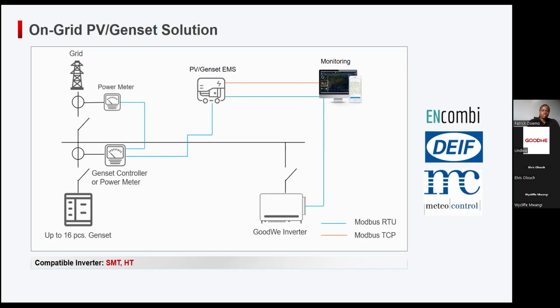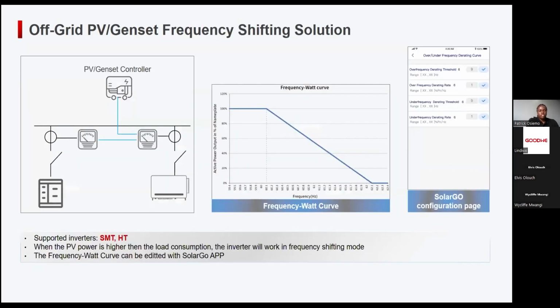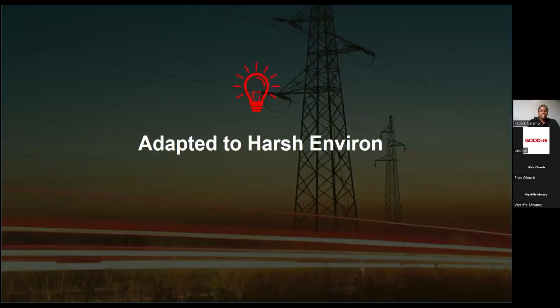One more feature that you can do with the PV integration is that our inverters can be controlled through frequency mode shifting. In this sense, when the inverters are generating more than the load, then through the frequency control, our inverter generation can be curtailed depending on the load, just to prevent any backfeed of power towards the generator. Therefore, you still maintain the efficiency of your genset, with minimum maintenance and less consumption of fuel, when you do the frequency shift control technique with our GoodWe C&I inverters.